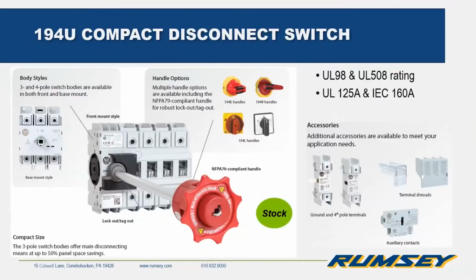The 194U disconnect. So this is relatively new. This is a non-fused disconnect. You can get it in 3-pole, 4-pole. It has your rotary handles there, and then an NFPA 79 compliant internal handle that can be used with lockout tagout. It's compact, panel savings. What makes this important is that it has 2 UL ratings, UL 98 and UL 508. So this can be used as a feeder disconnect for the panel, and it can also be used as a motor disconnect as well. So it comes also with your accessories and terminal shrouds, auxiliary contacts. And we're stocking these as well.